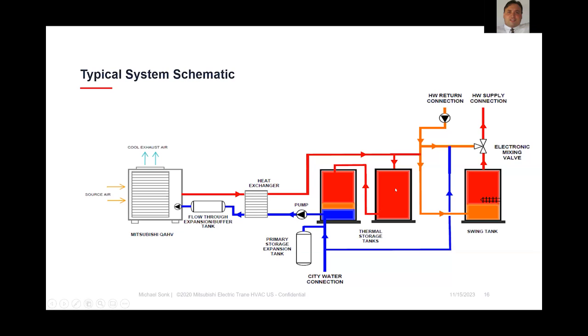And so this heat pump water heater, like I mentioned, is meant to operate almost at full demand capacity when it sees those tanks depleted, recharge the tanks, and then shut off. This equipment really is not designed and optimized for long, steady state periods of low delta T. That would be more indicative of a heat pump boiler for conventional heating hot water, and there are products like that you'll see coming into the marketplace in the near future. This is not that product.